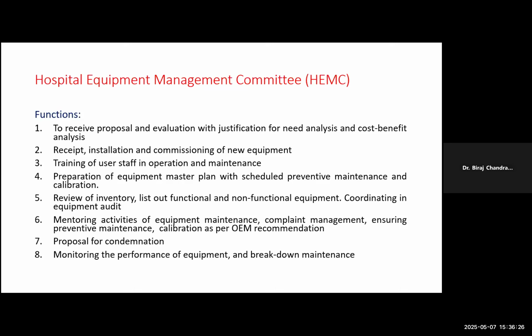Preparation of equipment master plan with scheduled preventive maintenance and calibration. Preferably, it should be technology oriented, or there should be software for maintaining all these things. Then review of inventory, listing out functional and non-functional equipment. So this committee should monitor, coordinating with the equipment audit committee also, and look after whether equipment audit is being performed or not. Monitoring activities of equipment maintenance, complaint management, whether breakdown was attended in time or not, whether some pending complaints are there or not, ensuring preventive maintenance and calibration as per OEM recommendation, that is, as per the manufacturer's instruction. Then proposal for condemnation.